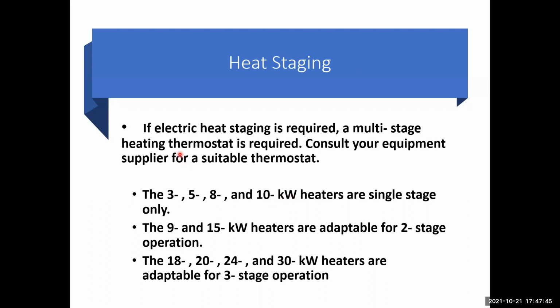Heat staging. If electric heat staging is required, a multi-stage heating thermostat is required. Consult your equipment supplier for a suitable thermostat. On our 3, 5, 8, and 10 kW heaters, those are for single stage only. 9 and 15 heaters are adaptable for 2-stage operation, and the 18, 20, 24, and 30 heaters are adaptable for 3-stage operation.